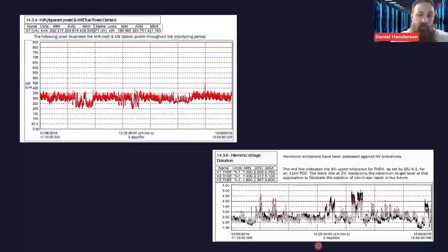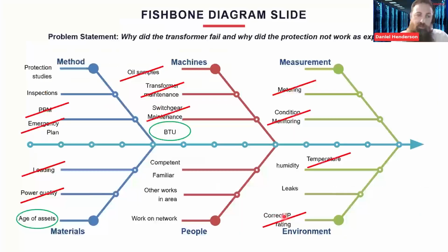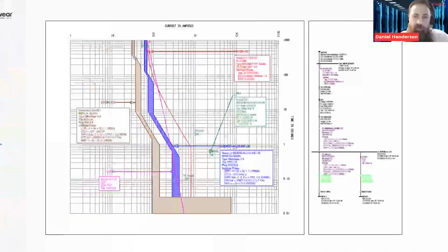Power quality. About 18 months before, I'd had a power quality study done on this asset. This is a typical week and nothing has changed on the network. From an 800 kVA capacity, the load sat at around 350 kVA, which again is quite a good load. I know it's not all of the power quality elements, but the worst bit was probably, on the LV side, the THDV. We normally have a 4% limit in line with G5/4-1 from an ENA standard in Europe. It was always below there, apart from the odd little spike above 4%. But again, nothing to write home about. So I would take loading off. I'd probably take power quality off. I'd be happy with that.